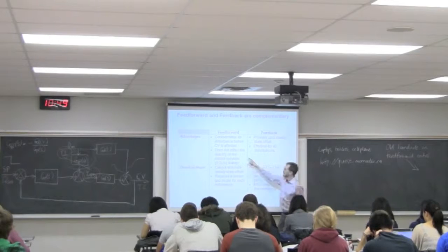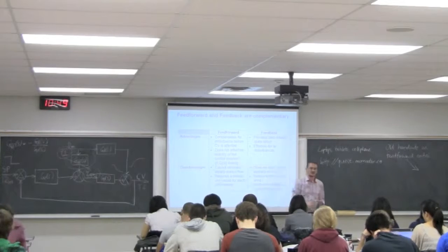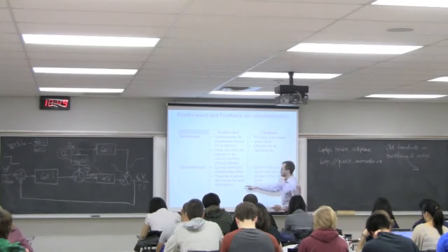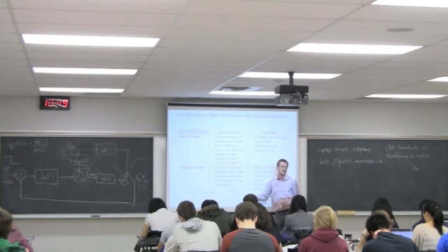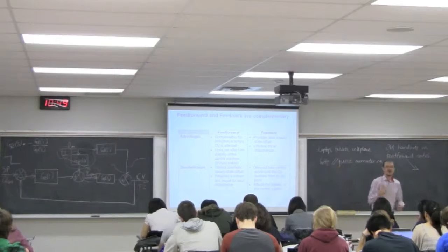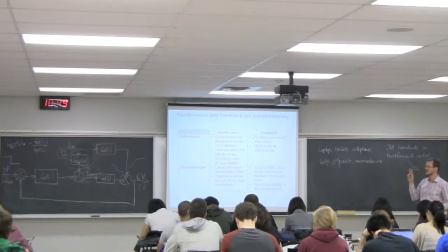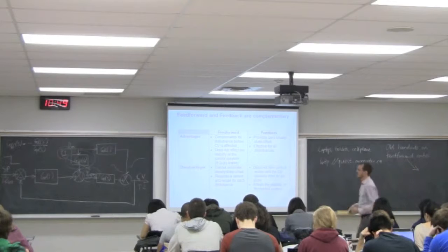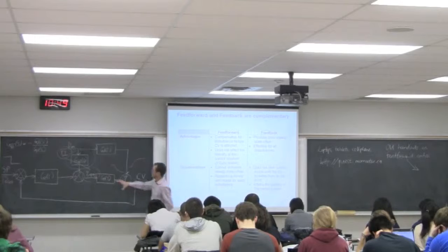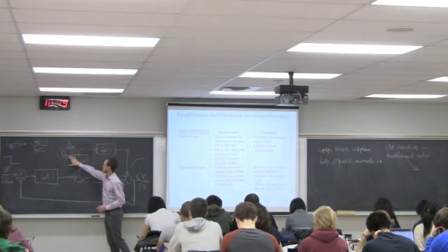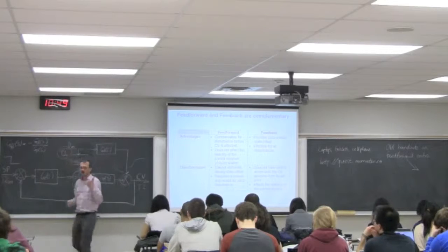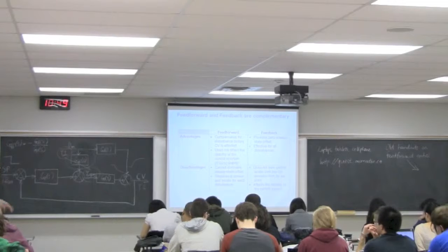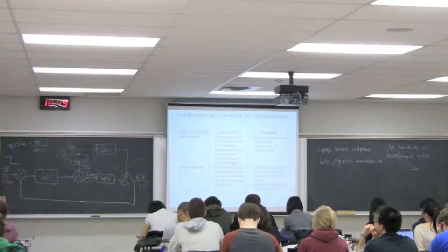Feedforward can only eliminate the particular disturbance for which it was designed. Okay. So each disturbance that you want to counteract with feedforward controller, you're going to need a sensor for that disturbance and a feedforward controller. Two things you need, the sensor and the feedforward controller. And if you want to have a feedforward on a different disturbance, say the flow, F1, you need a flow sensor and a flow feedforward controller for that disturbance. So every disturbance needs its own sensor and its own model.